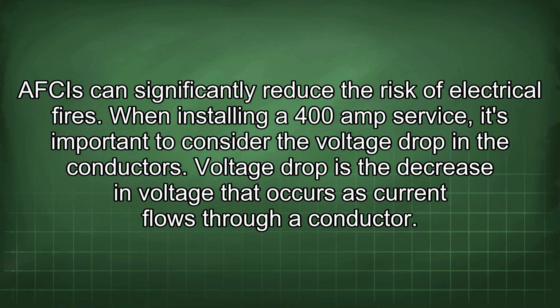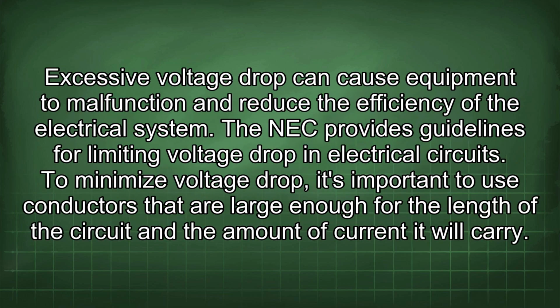When installing a 400 amp service, it's important to consider the voltage drop in the conductors. Voltage drop is the decrease in voltage that occurs as current flows through a conductor. Excessive voltage drop can cause equipment to malfunction and reduce the efficiency of the electrical system. The NEC provides guidelines for limiting voltage drop in electrical circuits. To minimize voltage drop, it's important to use conductors that are large enough for the length of the circuit and the amount of current it will carry.